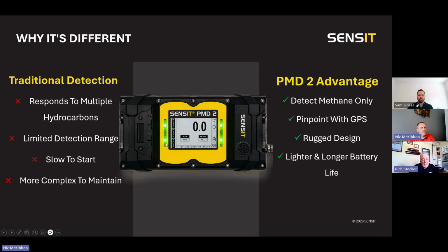Big difference, and the positives of going into the technology of the PMD2, as Nick alluded to. I'll talk a bit more in detail on how the TDLAS technology, or tuned diode laser absorption spectroscopy, works. But the big advantage of the PMD2 is it's methane-only detection. It will not see any other types of hydrocarbons. It emits a light wave that's only absorbed by the methane molecule. Therefore, you're not limited in when you can do your leak surveys based on cross sensitivity of the technology you're utilizing. Even infrared absorption technology is very good at low level methane selectivity, but at a certain level it will saturate the cell and become cross sensitive to other hydrocarbons, whereas the PMD2 is not cross sensitive to anything.